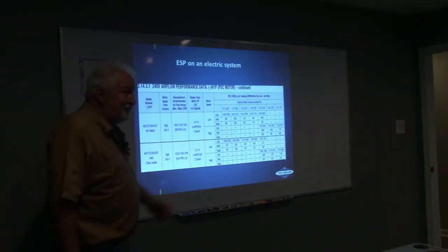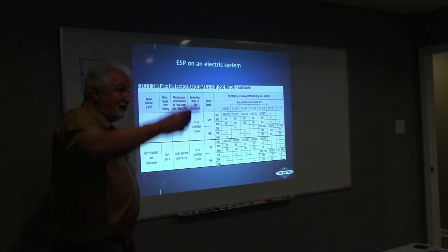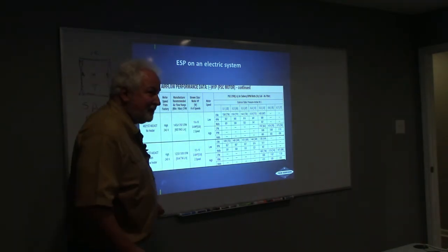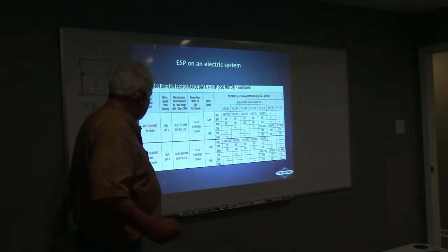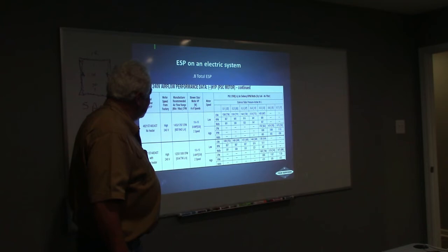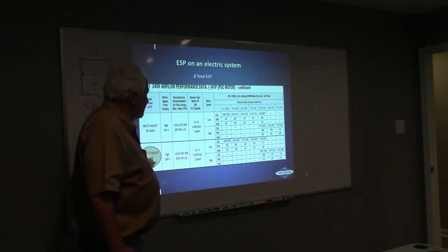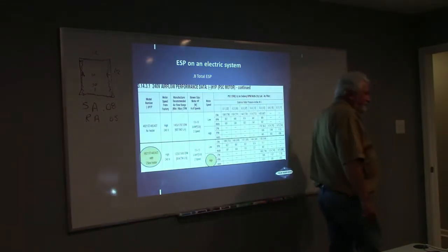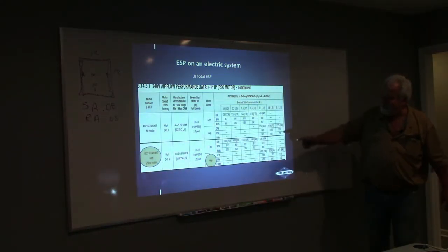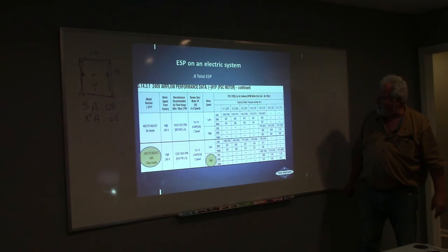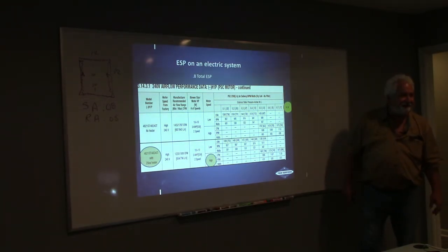You guys are not going to open it up. Mike's going to go up there and look at it, so he's going to break open the package because he's got superpowers. So he's going to go in here and he's going to look. The 0.8 total external static, he's going to look at the model number, go to 0.8, and that doesn't exist. Oh, what? He's going to go to high and go to 0.8. Oh, look, it's over here, it doesn't even exist.